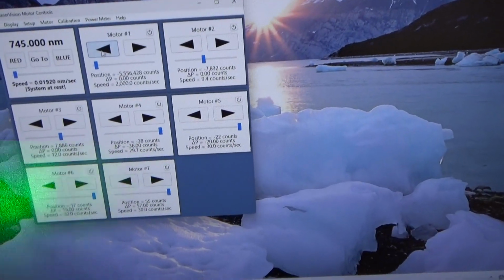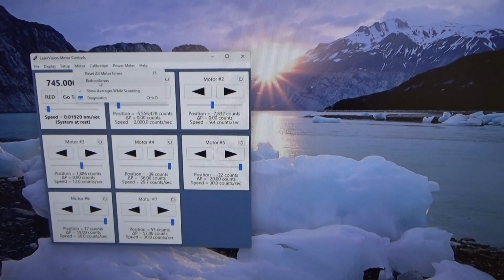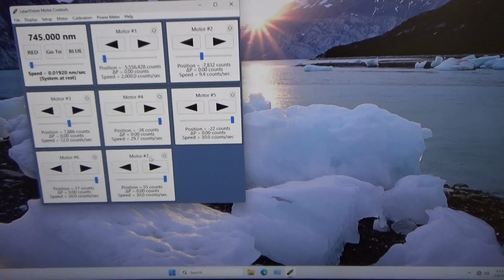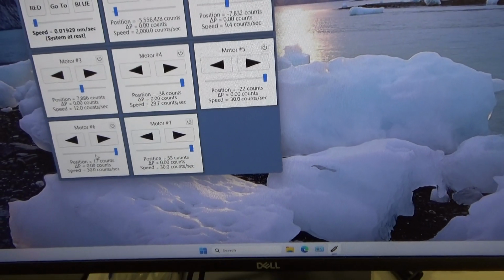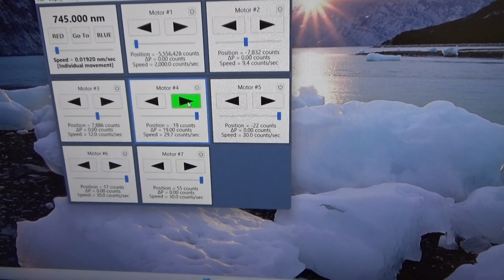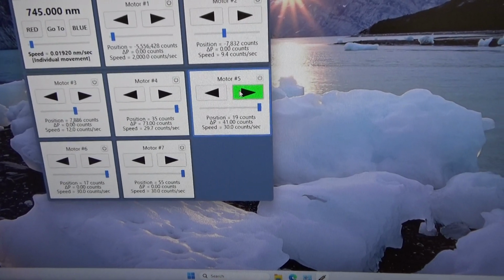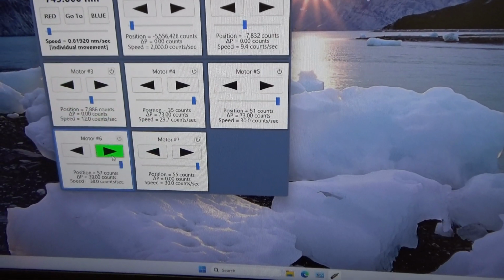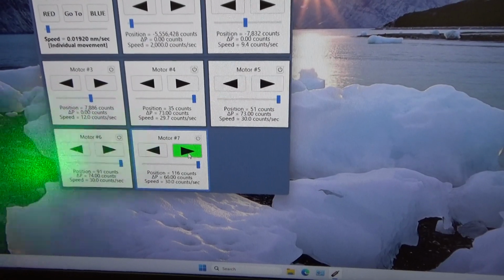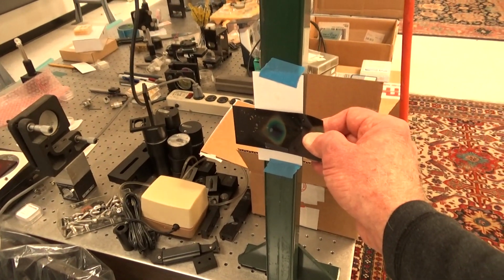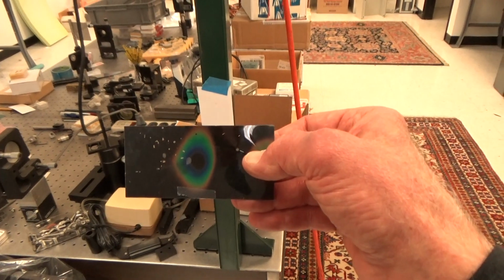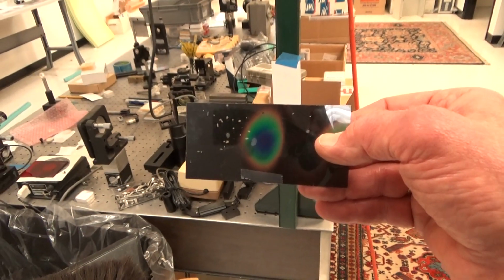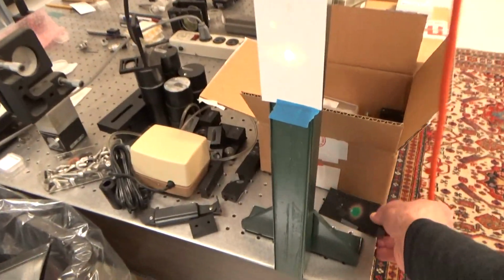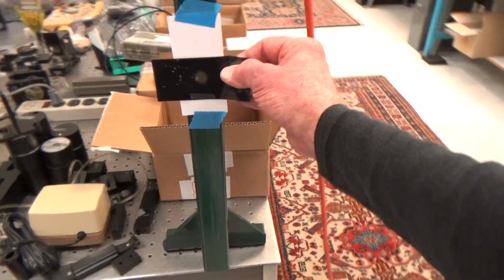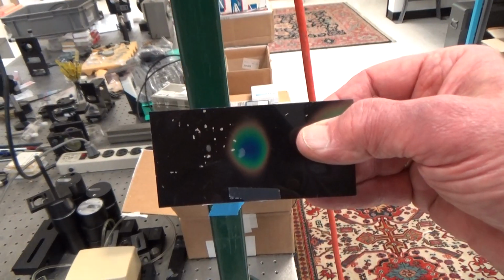So I'm going to adjust the crystals. First, I'm going to set all the motor errors to 0 so I can see how far I'm moving them. You can see the delta P here for each one of the OPA crystals is now 0. And I'm going to move each one of these crystals clockwise by 70 some points. Okay. Now I'll go back and look. It actually did better. Try that again. Yeah, no, I actually think that's pretty good.